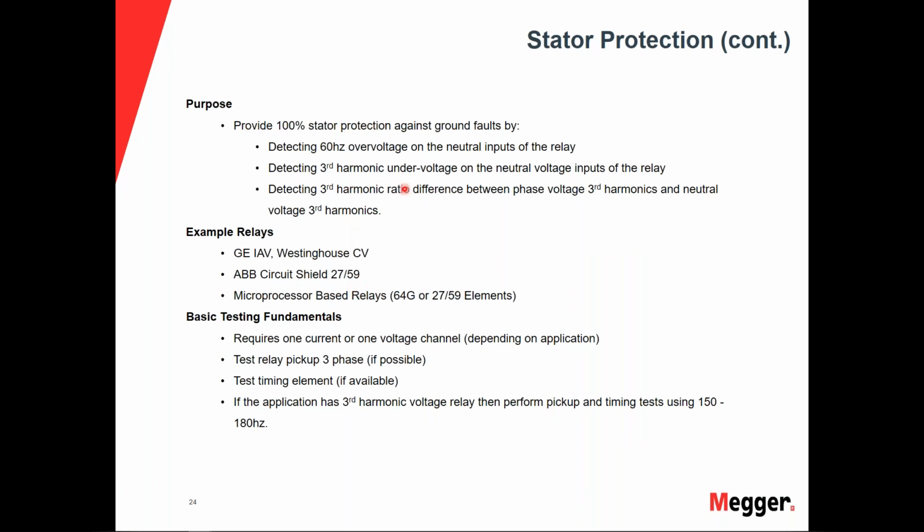The purpose, we just went over this. The purpose of it was to be able to detect the third harmonic undervoltage, and allow us to get the 100% coverage using what's inherent to the generator itself.